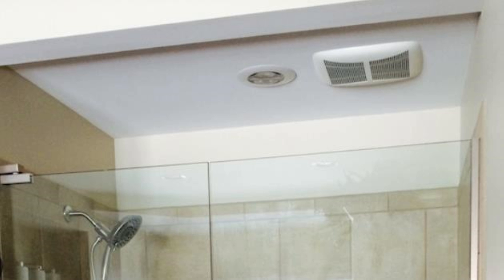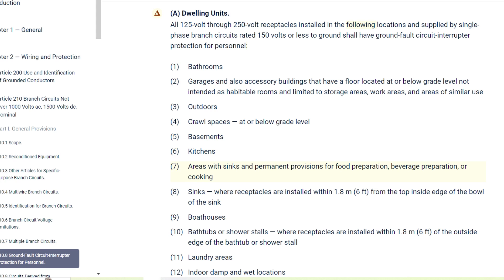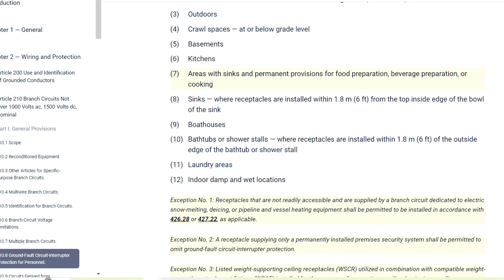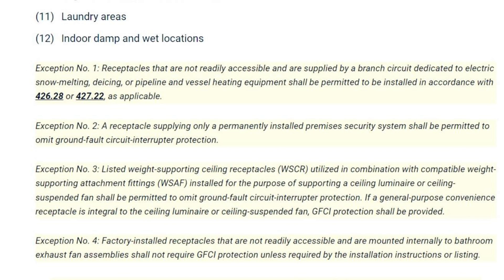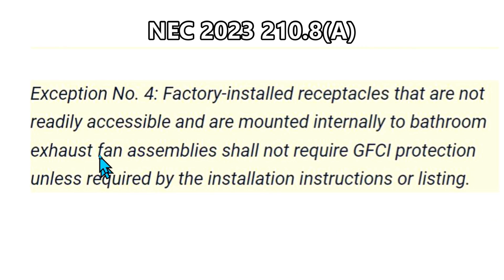Can a bath fan be installed directly above a bathtub or shower? Let's scan down to the bottom of 210.8A, past the language where the article demands that 12 areas must have GFCI protection for dwelling units. Here we see four exceptions to article 210.8. The one we are interested in for bath fans is the last exception.